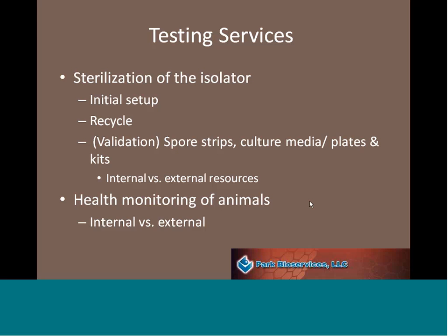Then, do you just sterilize it and take it on faith that it's sterile? That's not a good idea. So what is required is to do validation. You have things like spore strips and other biological indicators. If you have access to a bacteriology lab, you could use your own broth, your own media. So those would be some alternatives.